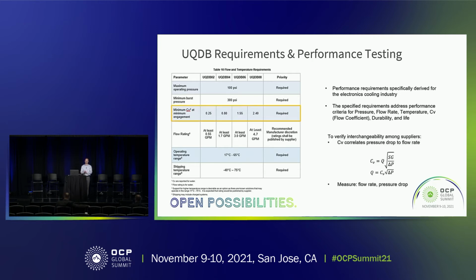So looking at this requirement table a little more, I think the key metric here when you're looking at a universal disconnect is its performance, and not just, does supplier A perform well when you use supplier A parts, but does supplier A perform well when you combine it with supplier B? So the focus of this testing is to look at this CV value and to verify that no matter what suppliers are mated with each other, that they meet or exceed that minimum CV value, depending on size. A quick background on what CV is and then how we measure it, and then I'll dive into kind of the testing methodology and setup and test fixturing.